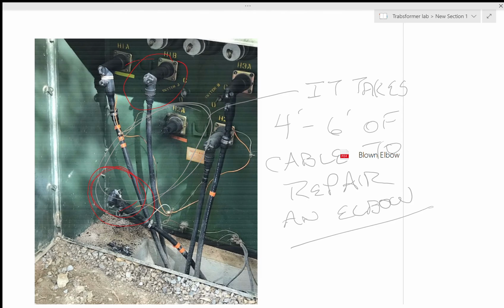This happened over in Alamogordo about 2 or 3 weeks ago. They lost power to their campus, and luckily, down in their vault, they had some spare cable, so they came up, they cut off about 2 feet of cable, and they started making another elbow with 2 more feet of cable. So typically, it takes 4 to 6 feet of cable to repair an elbow, and it depends on how far it's burned back. Notice that this is the B phase. In this case, 1 wrap of tape is the A phase, 2 wraps of tape is the B phase, and 3 wraps of tape is the C phase. Supposedly. Anyway, that's what's going on.